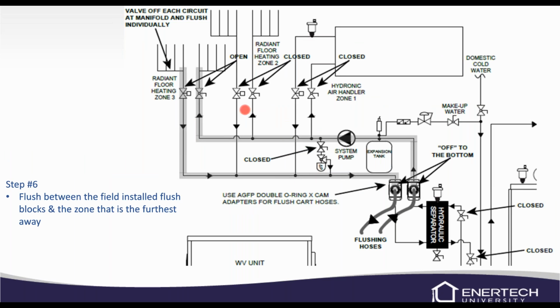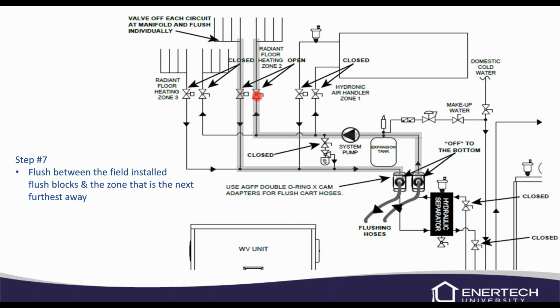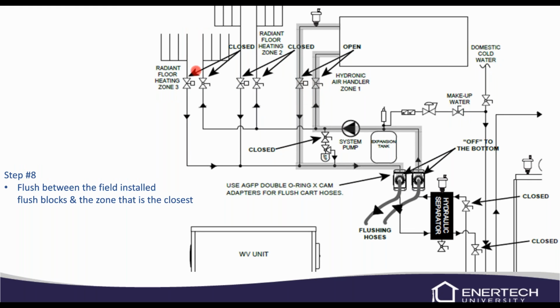The next is we're going to flush between your farthest zone away. So close off any other zones that are closer, and close off your bypass little circuit here, and we'll flush through your zone. And obviously just flush through till all the air's out. Then you're going to want to close these off, and you're going to want to flush your next closest zone, and so on until all the zones are flushed.